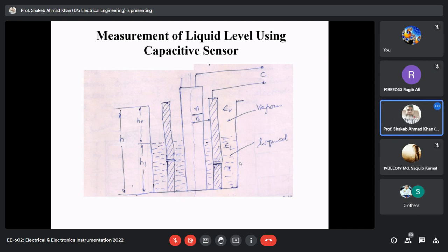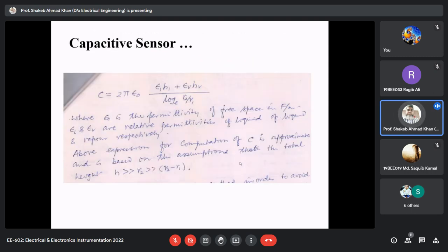I'm asking about viscous liquid, we are talking about insulating liquids. If the liquid is conducting, then obviously your capacitance won't work, both the electrodes will get shorted. Am I right? Yes. So the scheme I am discussing here is only suitable for non-conducting, means insulating liquids. If your liquid is conducting, both the electrodes will get shorted and it won't work.